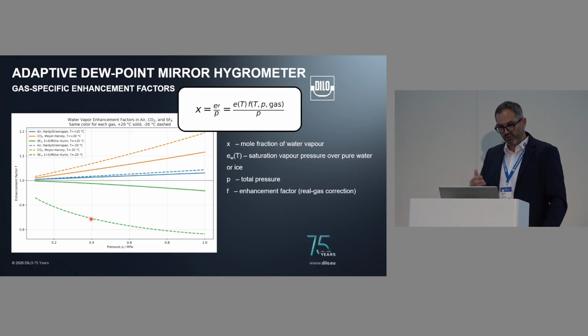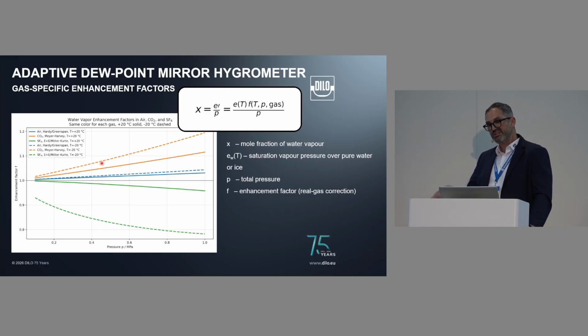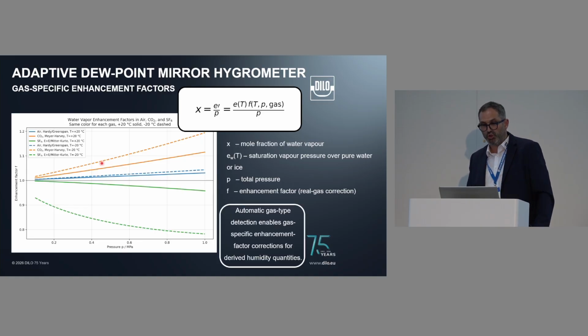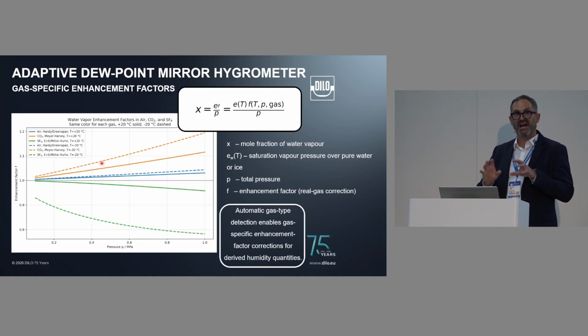If we measure in SF6, we would have a reduction in the mole fraction of, for example, 15% at minus 20 degrees C. If we compare that with CO2 at minus 20 degrees C, this would still make an error of, let's say, 6, 7, 8% or so. So it's quite important that you can include this, and the automatic gas detection enables us to include those specific enhancement factors.